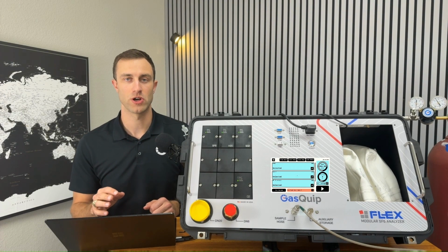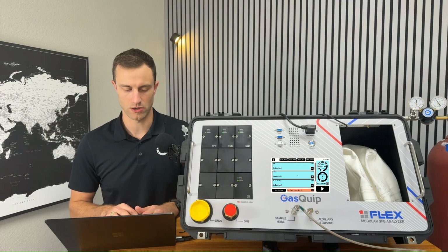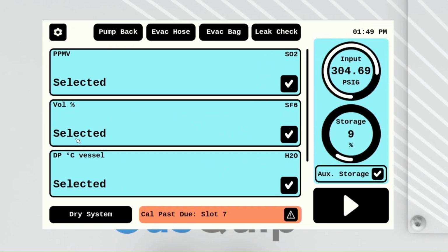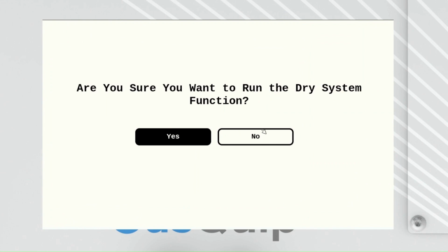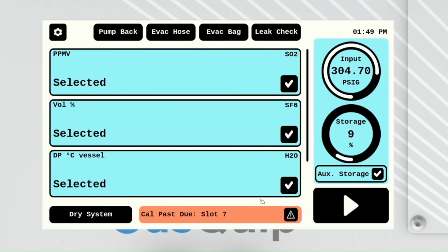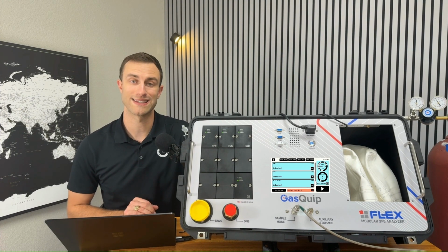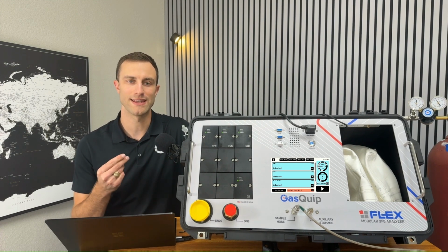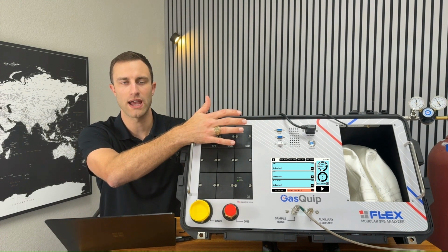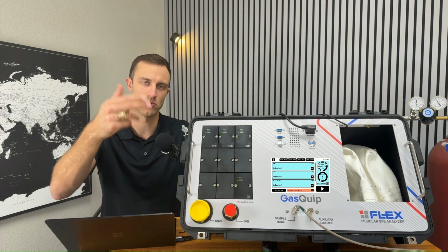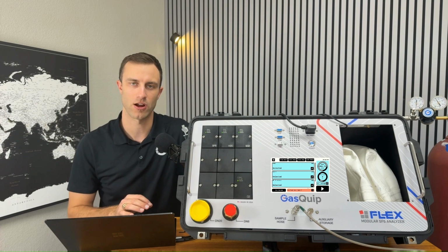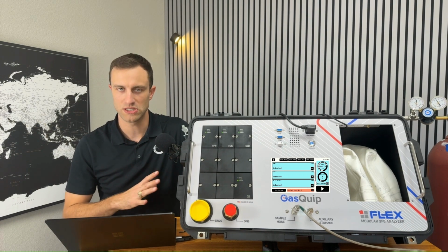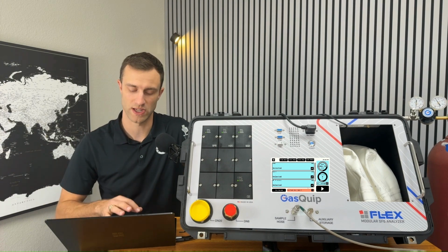The next thing that I would do is run a dry system. So let's go back to our analyzer close up. That's going to be down here in this bottom left. That's going to pull a vacuum on all of our major components on the system for about 5 minutes and try to help burn off and boil off some of that residual moisture that could be hanging around. This is more for the spikes in moisture that you can see. So it's going to run the heated tip on the H2O sensor and also run the pump inside to evacuate any of the residual moisture that's inside of there for about 5 minutes. And that should help start you out of a clean slate to then do new tests.